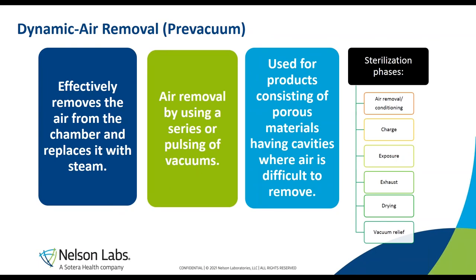Pre-vacuum steam sterilization is referred to as dynamic air removal. There is also a cycle type called steam flush pressure pulse, which is also dynamic air removal but does not employ vacuums. With pre-vacuum, as the name implies, vacuums effectively remove air from the chamber, replacing it with steam through a series of steam pulses and vacuums. It's used for products with porous materials and cavities where air is difficult to remove.